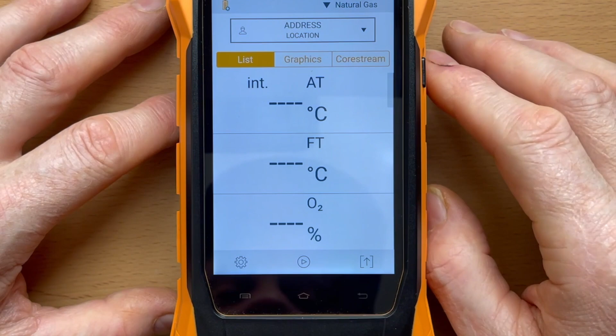Zero in the gas sensor - you press it and it zeroes all the sensors and goes through the purge procedure. The average on, we don't know whether this is for when you're taking a room sampling, so if you know what average on is, let us know in the comments below. I personally think it's when you're doing a room test and it takes the average of your readings, but we're not going to go through that because it goes through a procedure.